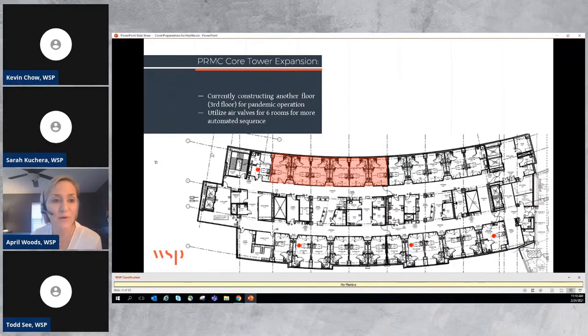And this can be great for other reasons outside of a pandemic, potentially just during a seasonal flu, if they have a need for some isolated patients that maybe don't need the airborne isolation room, they can use those 6 rooms. On this floor plan, I also have 4 red dots. Those are the permanent airborne isolation rooms. So of course they do still have those on the floor. And then we did design this floor to be flexible so that it can be fully exhausted as well through the different sequence of operation.